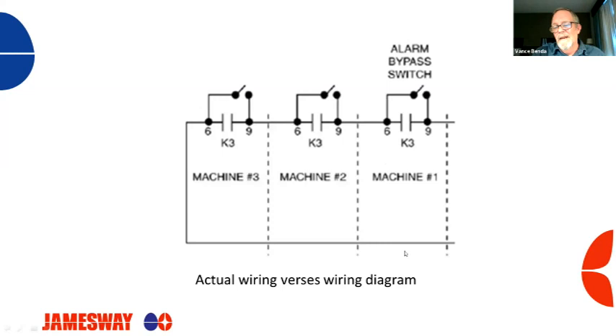I want you to realize that this wire and this wire in the real world are going to be contained in one two conductor. So this two conductor is going to come in. One of your wires is going to connect to this terminal, and then this wire is going to come in and have another connection right here, so that it can connect to the two conductor that's going out and over to the next machine. So another terminal is going to be connected here and go out and over and connect to the next machine, and so forth and so on. So that's your loop, and where all this length comes from is all that wire you have to pull.